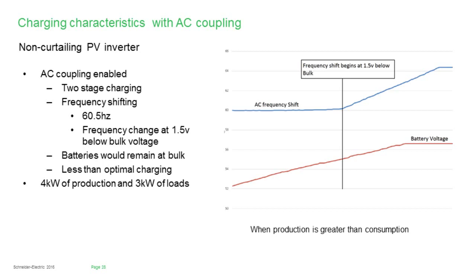And so we can leverage that idea with the non-curtailing inverter by simply frequency shifting 1.5 volts below the bulk set point within the XW Plus or SW. And so what's going to occur is that as the voltage gets above 1.5 volts below the bulk voltage, that frequency is going to start to shift. And it's going to keep shifting until we reach that bulk voltage, and we're going to get to 60.5 hertz. At that point, of course, the IEEE 1547 PV inverter is going to disqualify that AC source and stop producing power. Then the battery voltage will start to decline, and then that frequency will also begin to decline. And the end result is that the system is going to start requalifying the AC source produced by the Schneider Electric inverter.